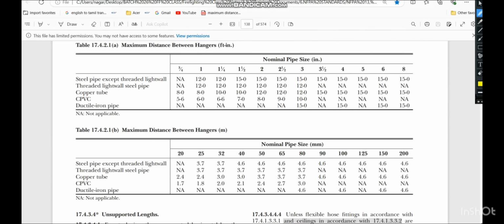And when it comes to the maximum distance between the hangers, we have to follow this NFPA 13 rule strictly. For example, here it is given in feet and inches, here it is given in meters. The first one is steel pipe except the threaded one. Second one is the threaded pipe and copper tube, CPVC, ductile iron pipe. So all these pipes are allowed to be used in firefighting systems. Mostly we are using carbon steel pipe for the above ground application.